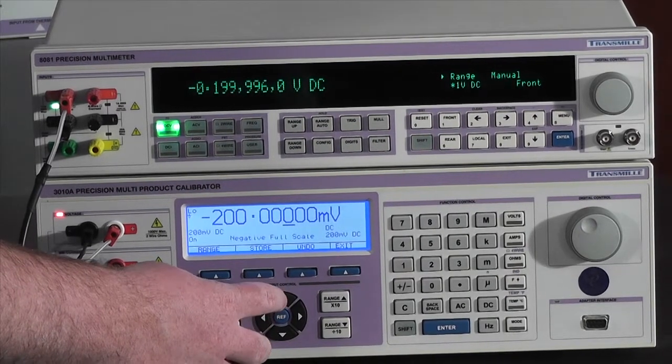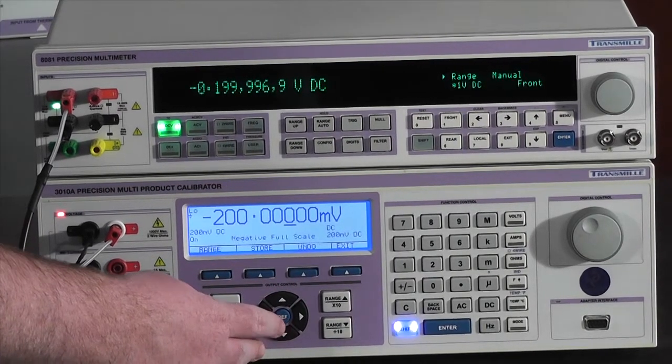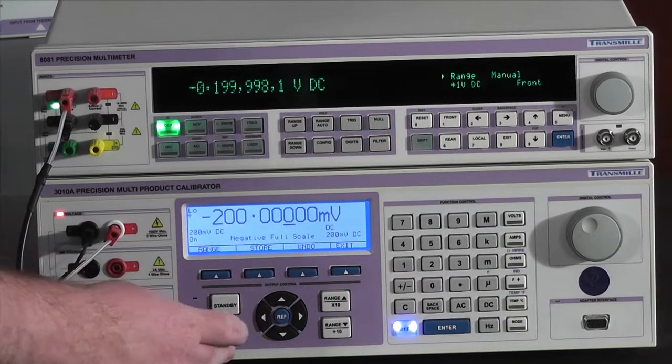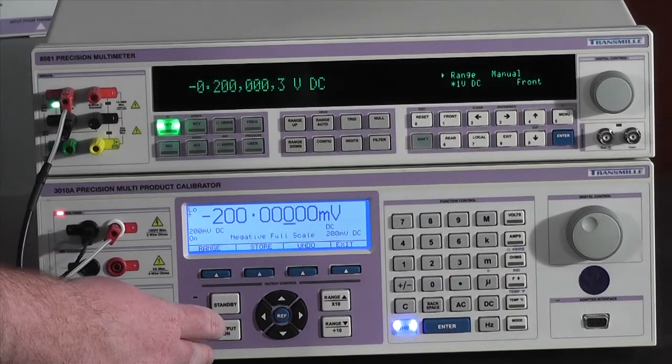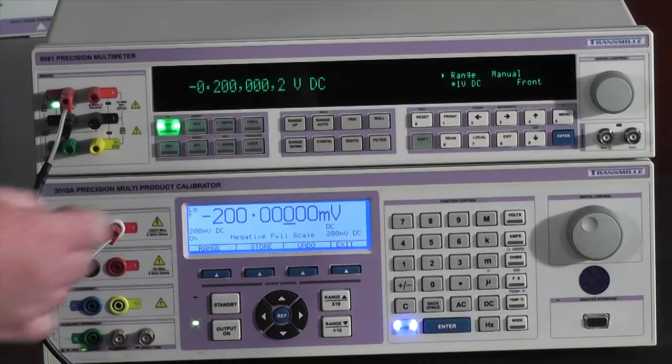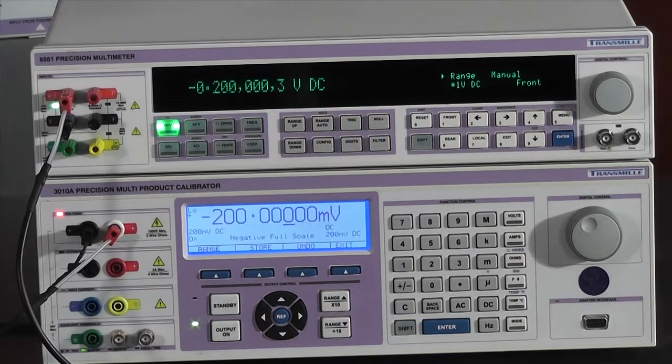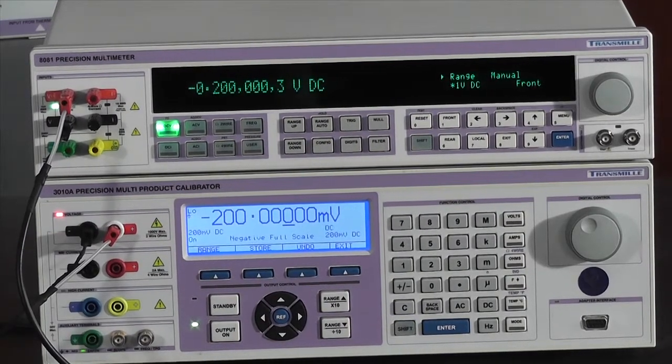Once again, simply adjust whichever way is most convenient until desired value is reached on the screen of your multimeter. Pressing store will store all calibration adjustments.